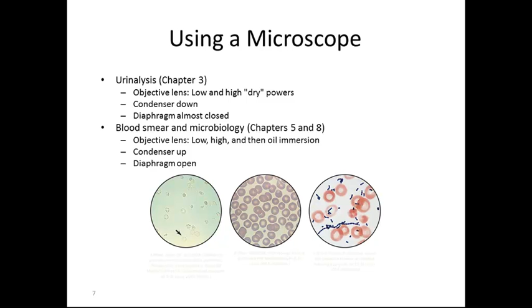Proper care after use of the microscope. All slides should be discarded. Clean objective and ocular lenses with lens paper and solution. Turn off your microscope. Lower the stage down all the way. The lowest power objective should be locked into place and cords should be wrapped. Microscopes should be placed back into the assigned number cubby with the arm facing out. And all microscopes are labeled with a number on the back side on the arm. And that number should match the cubby number that you are putting your microscope in.